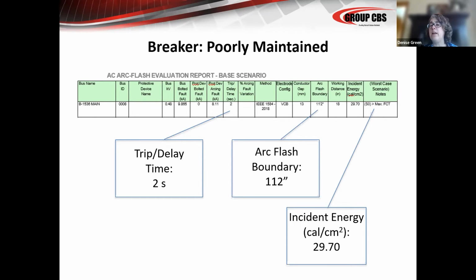So just that small amount of time on even a delay, when I talked about a delayed trip, can cause a serious situation to the equipment itself, because now your incident energy availability is so much higher. The fault is ramping up exponentially.